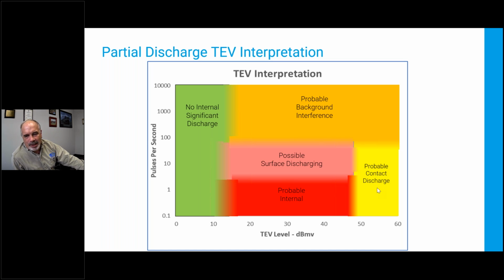The last is the possible contact discharge. Contact discharge, or floating metal discharge, is where I have metal in the high voltage field. And that metal acts like a perfect TEV source and creates a lot of discharge. It won't necessarily lead to failure, but it masks all the lower level signals and makes it harder to see.